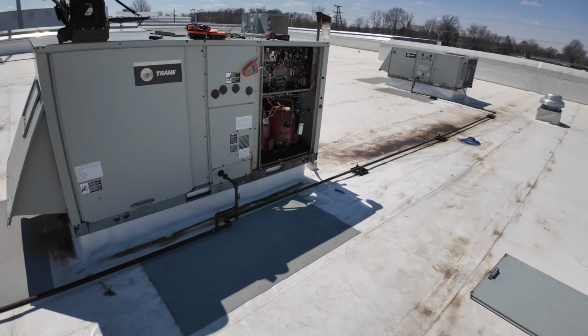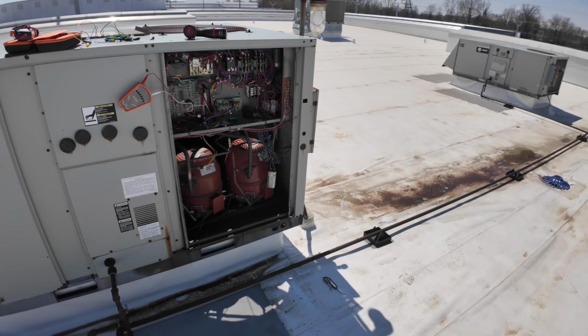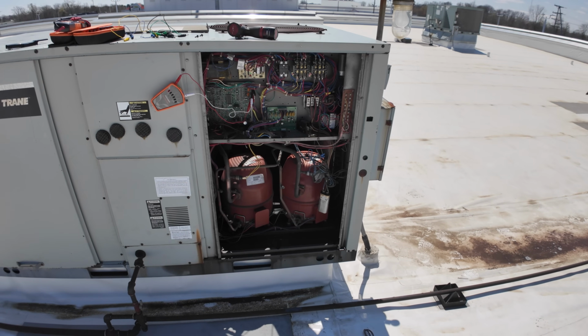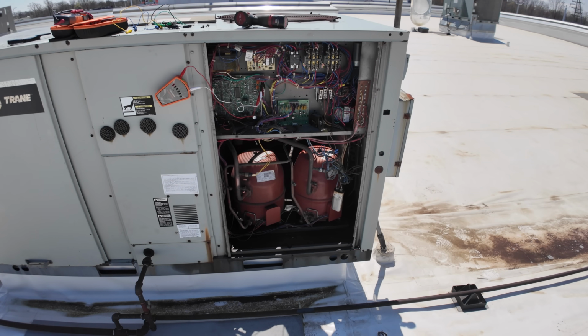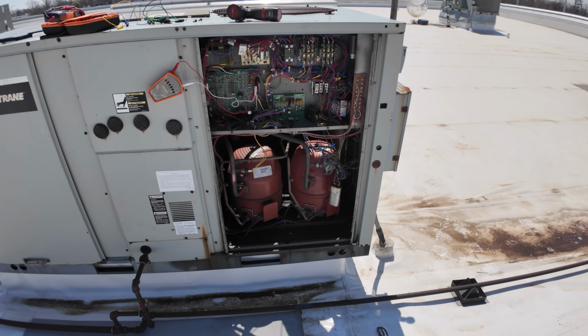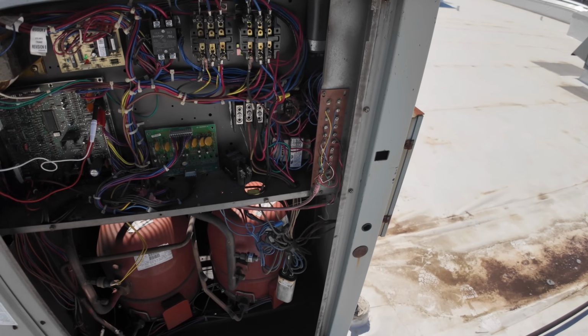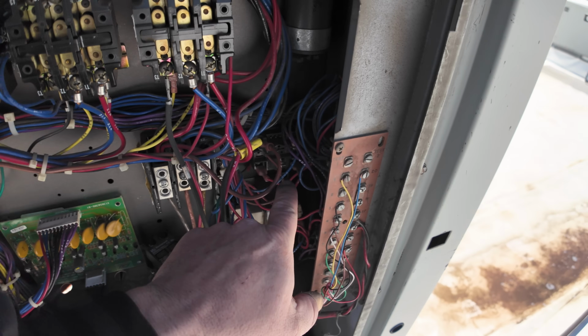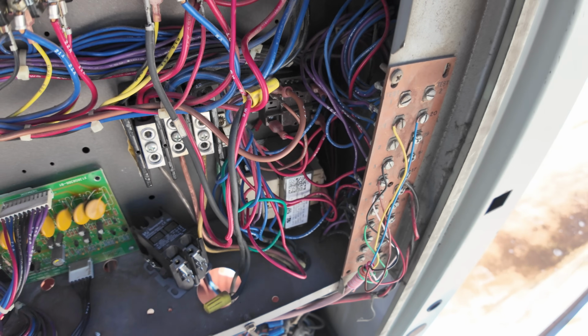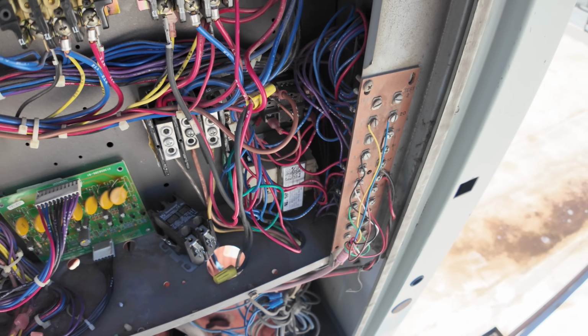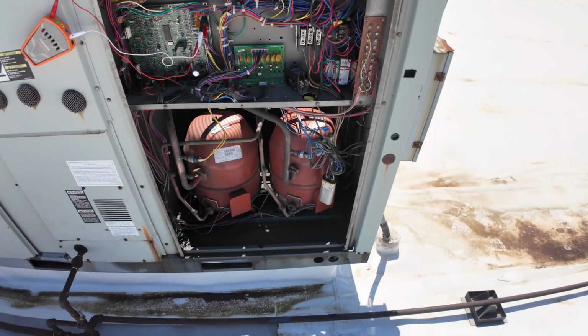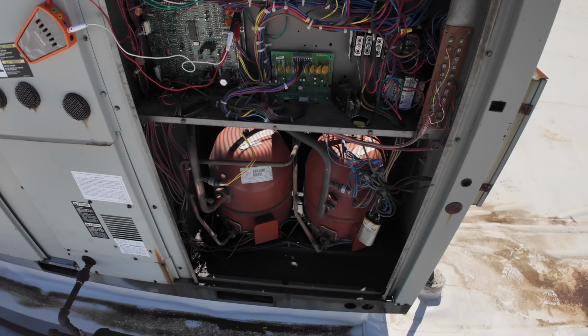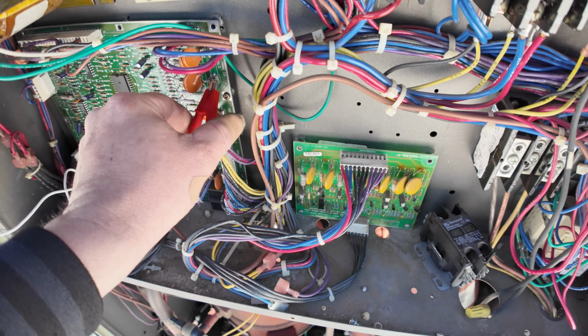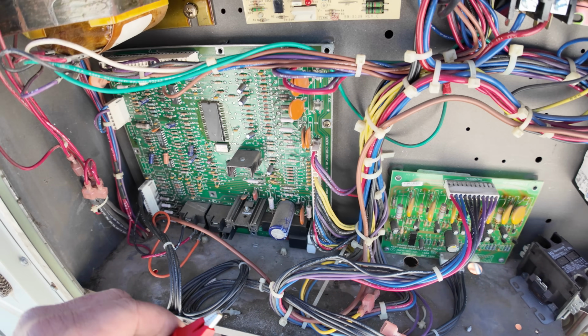All right guys, we're up here on a no heat, no cool, whatever call. I'm not really sure which one they're complaining about because the thermostat's blank, so I just got started. This has a history of supposedly tripping a fuse, and they found this relay coil on that relay there, that Honeywell, to be the problem back in December. Well, here we are mid-April, and I come up here and look at it, and the fuse is completely missing, which I always love it when somebody gets in there and jacks with stuff.